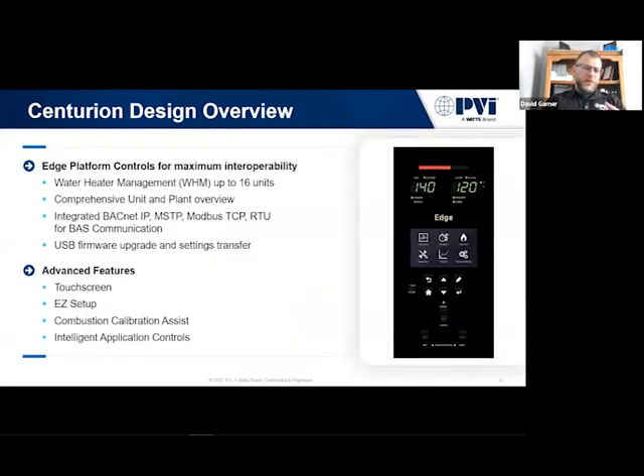In addition to that load matching, we could have varying flow rates up and down, and this unit's not going to short cycle because it could load match exactly what's happening out in the system. The controller itself is extremely powerful. It can have up to 16 units communicate itself. We don't need a standalone controller on the wall. Everything can network through this single controller.